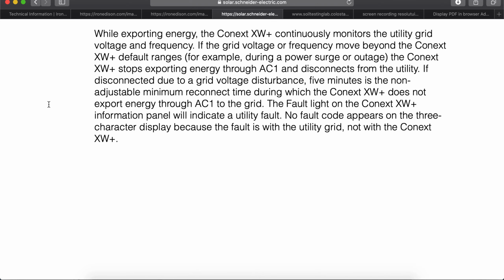While exporting energy, the Conext XW Plus continuously monitors the utility grid voltage and frequency. If the grid voltage or frequency move beyond the Conext XW Plus inverter's default ranges, for example during a surge or outage, the inverter stops exporting energy through AC1, that's the grid input, and disconnects from the utility. If disconnected due to a grid voltage disturbance, 5 minutes is the non-adjustable minimum reconnect time during which the Conext XW Plus does not export energy through the AC1 to the grid. The fault light on the Conext XW Plus information panel will indicate a utility fault. No fault code appears on the 3-character display because the fault is with the utility grid, not the Conext XW Plus.